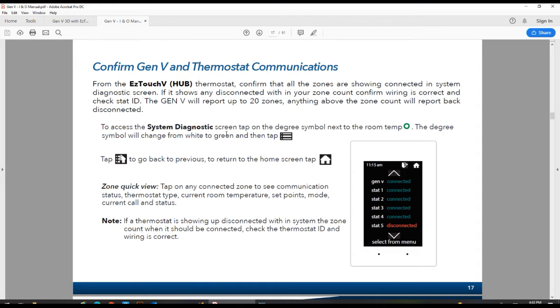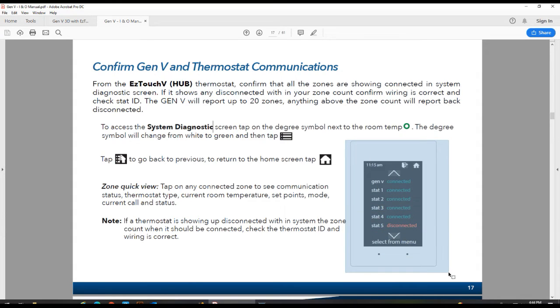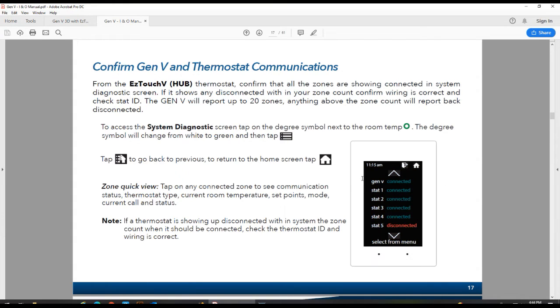Go ahead and from the hub thermostat, you'll tap on the 3 white bars in the right hand corner, and you're going to go to the system diagnostic option within that menu. Once you're in there, you're going to see a screen that looks similar to this, and this is our diagnostic screen confirming that we are connected and communicating to our Gen V controller, and in this case 4 zone thermostats that are tied to it.